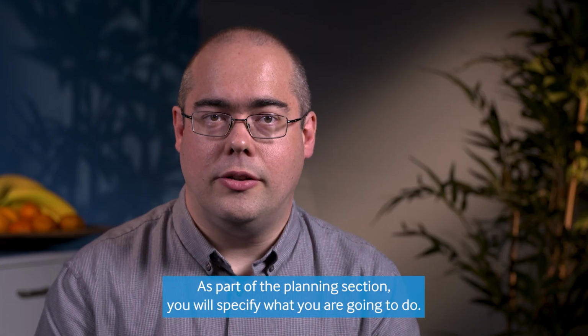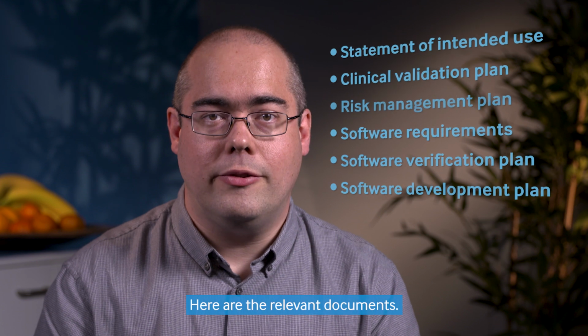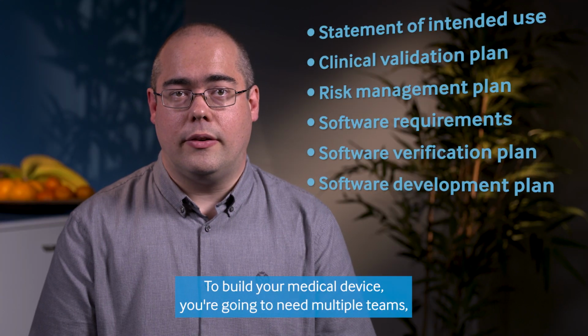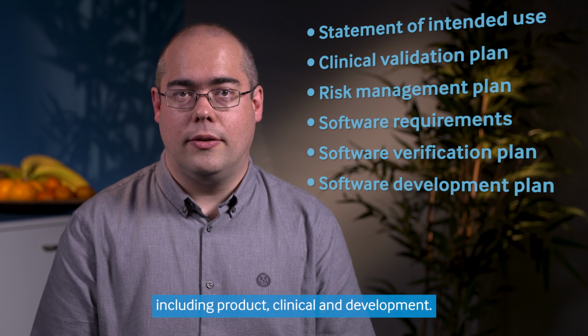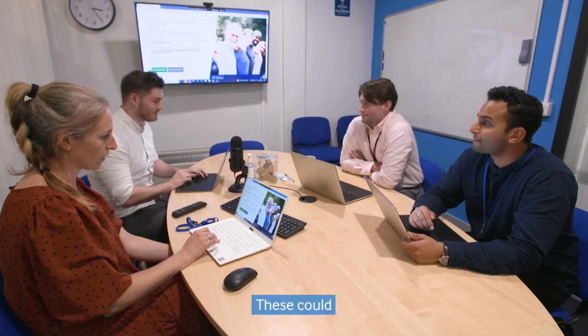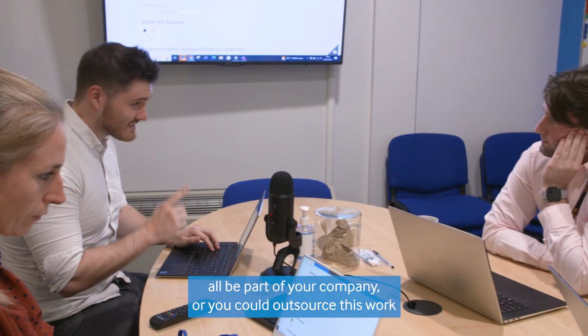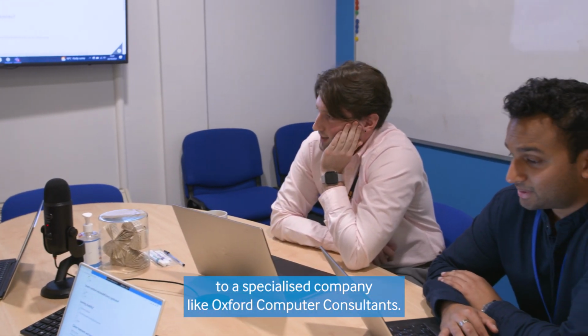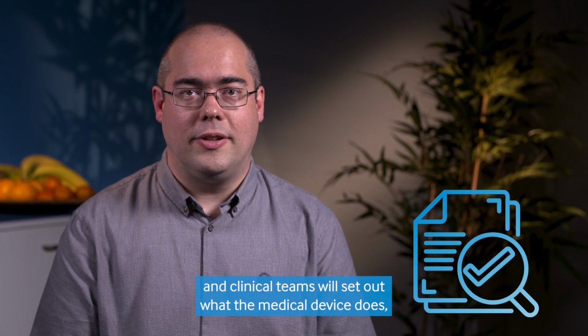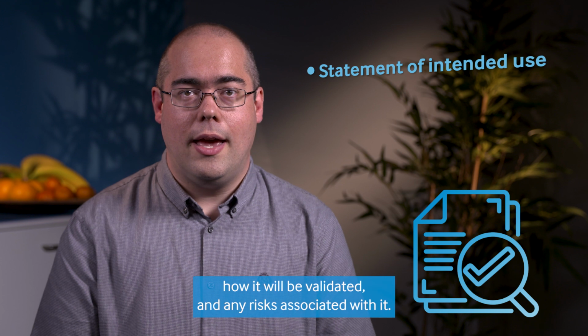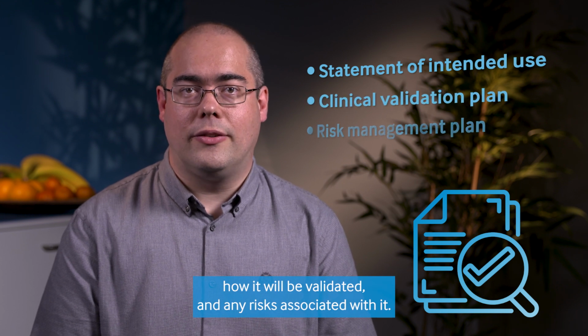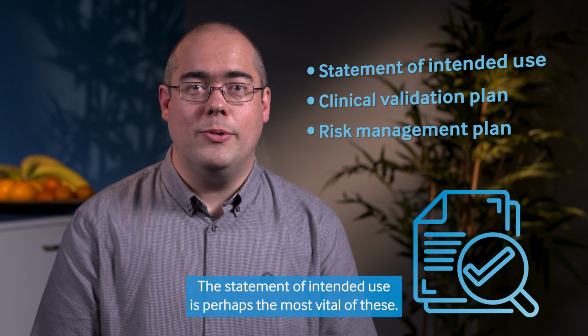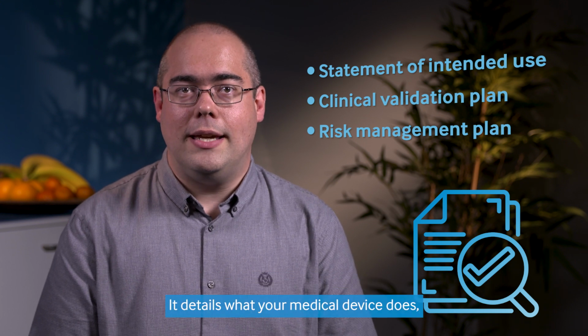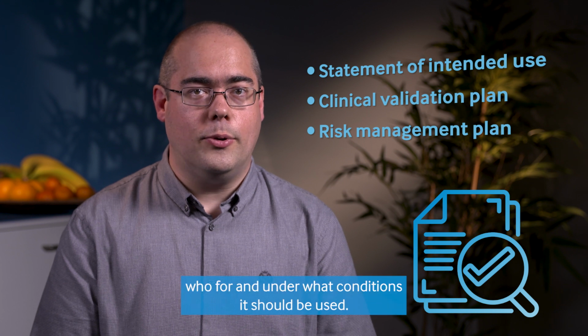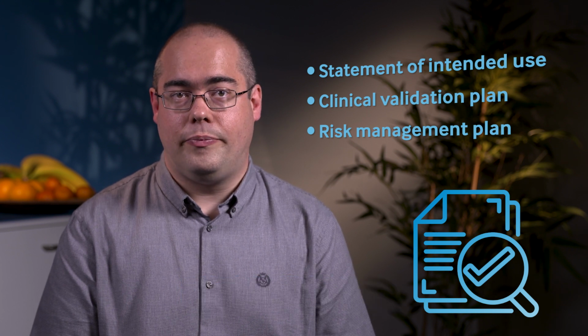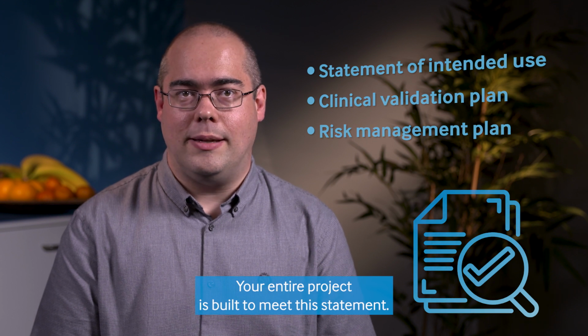As part of the planning section, you will specify what you are going to do. Here are the relevant documents. To build your medical device, you're going to need multiple teams, including product, clinical, and development. These could all be part of your company, or you could outsource this work to a specialised company like Oxford Computer Consultants. In the first 3 documents, the product and clinical teams will set out what the medical device does, how it will be validated, and any risks associated with it. The statement of intended use is perhaps the most vital of these. It details what your medical device does, who for, and under what conditions it should be used. Your entire project is built to meet this statement.